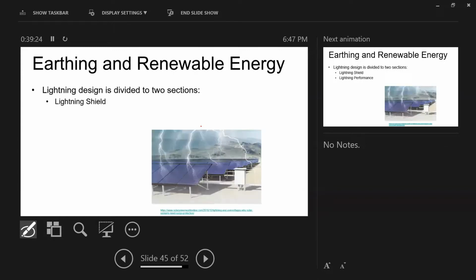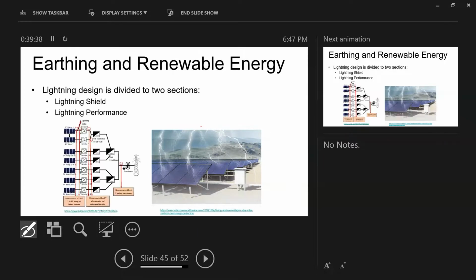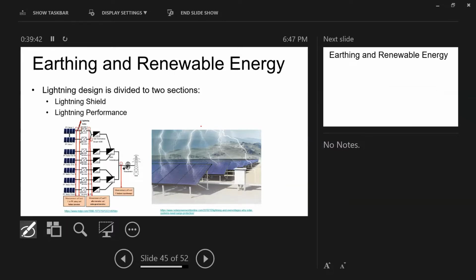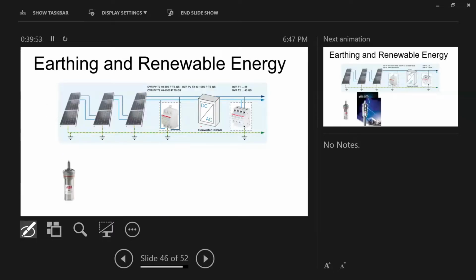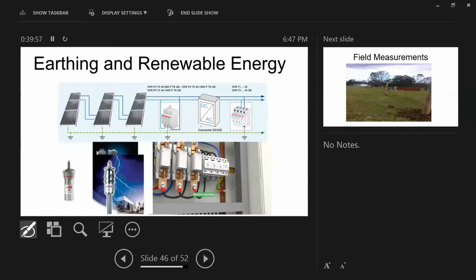So when it comes to lightning, I have a lightning shield, and I will also have lightning performance. Lightning performance, if your lightning shield fails, will determine what protections I can put in after the shielding, after a direct lightning impact. Here I can put surge protection, lightning protection. It's a second protection line. And by the way, guys, as you can see, everything cannot work without your famous earthing system. Everything.